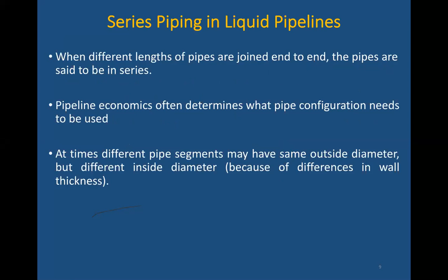Then we saw what series piping is, and what the importance of series piping is, and we also calculated the equivalent length in case of series piping. We can remember that equation: total pressure loss equals 6.2475 into 10 to the power 10, F L U square into SG by DI to the 5. Once you simplify all this, you finally get LE equals LA plus LB into (dA by dB) to the power 5. We already discussed this in detail in the last class.